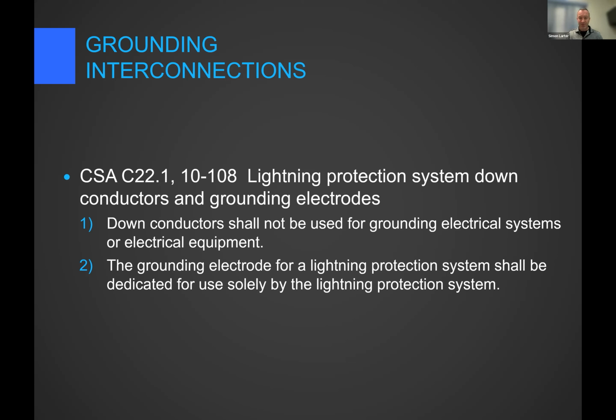The grounding electrode for a lightning protection system should be dedicated for use solely by the lightning protection system. This is not meant to preclude use of a ground loop conductor, just for interconnecting everything. We will connect to those. We'll come down, we'll drive a ground rod, we'll connect to the ground loop conductor. That's an interconnection. That's not us using the ground loop conductor for our lightning ground.